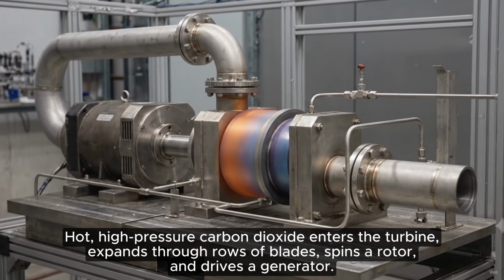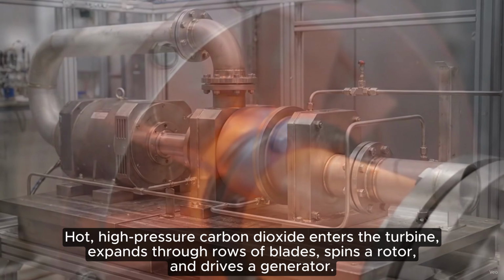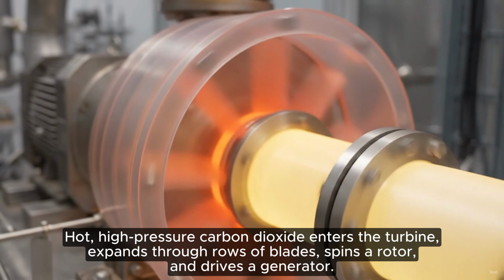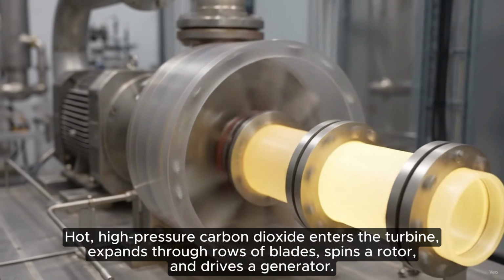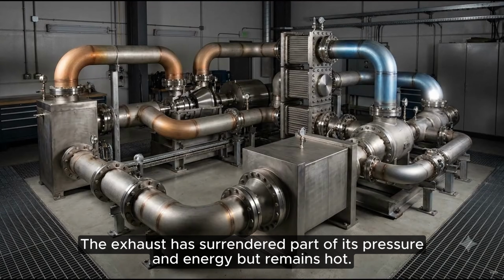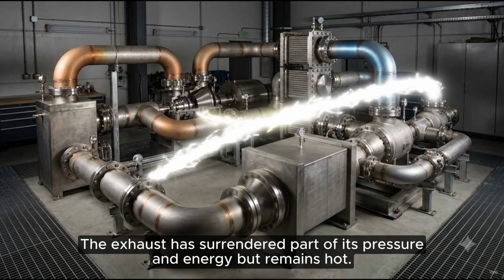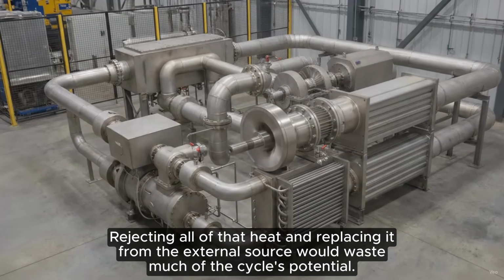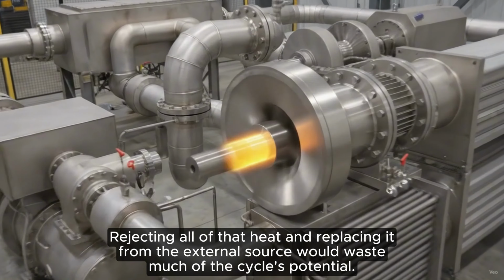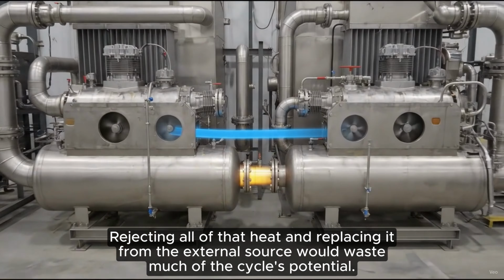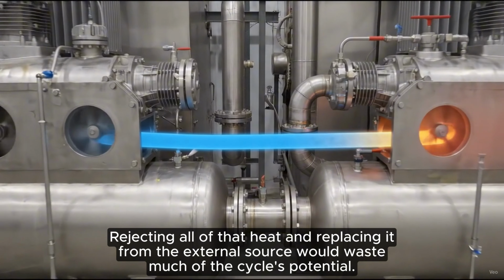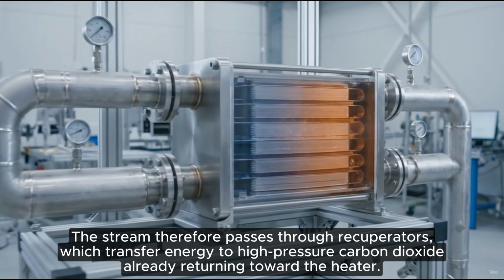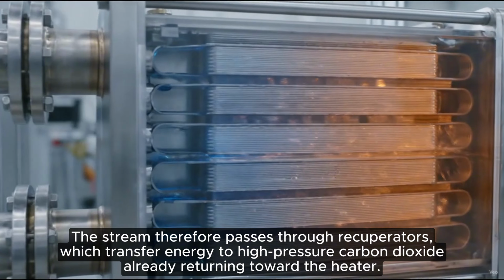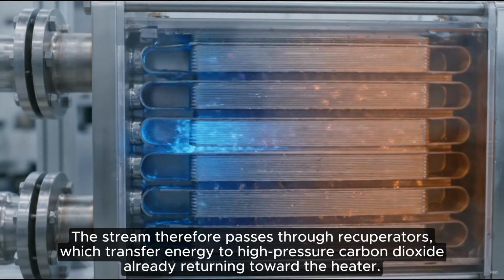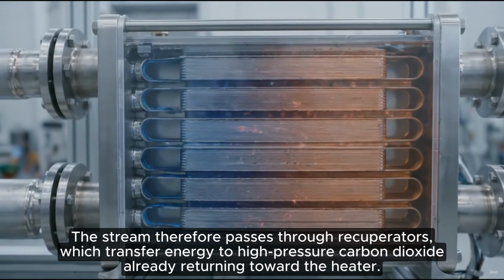Hot, high-pressure carbon dioxide enters the turbine, expands through rows of blades, spins a rotor, and drives a generator. The exhaust has surrendered part of its pressure and energy, but remains hot. Rejecting all of that heat and replacing it from the external source would waste much of the cycle's potential. The stream therefore passes through recuperators, which transfer energy to high-pressure carbon dioxide, already returning toward the heater.